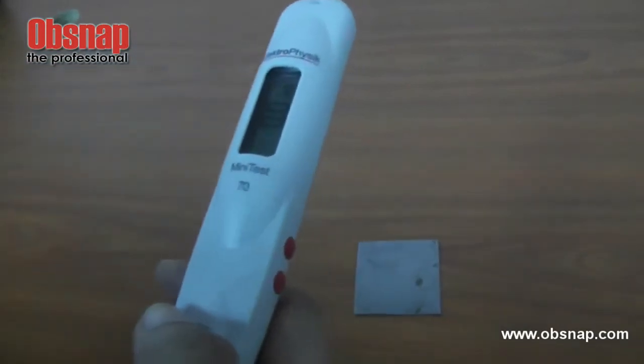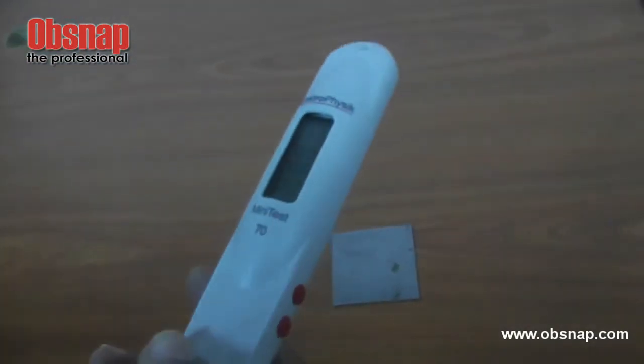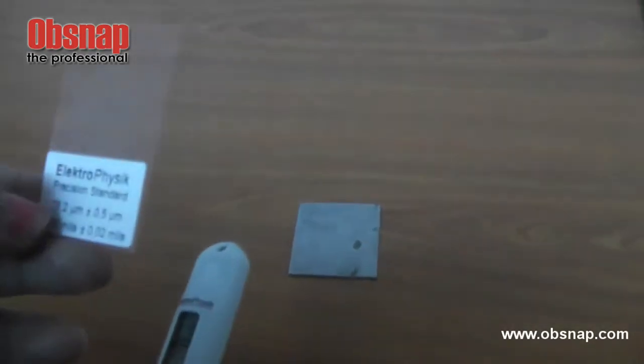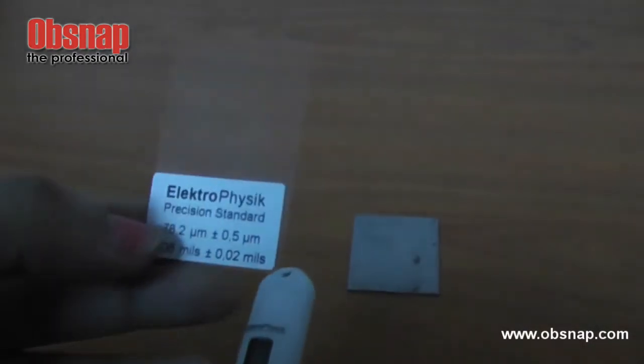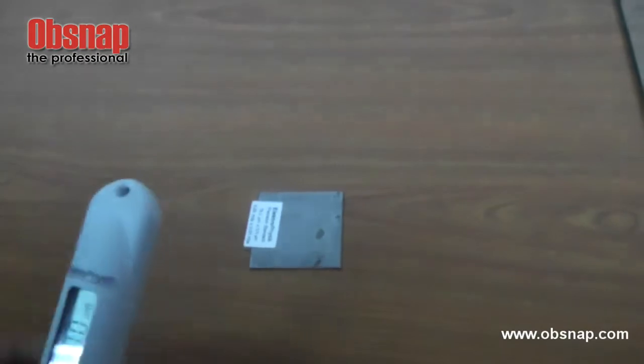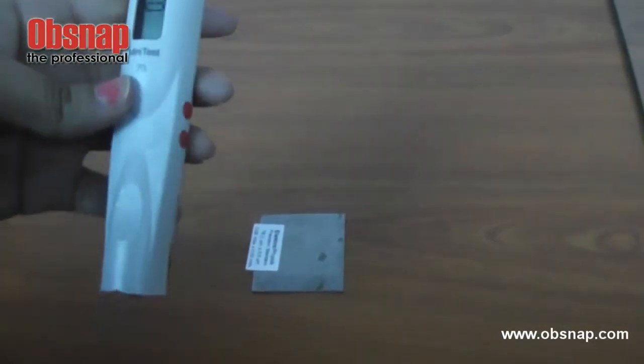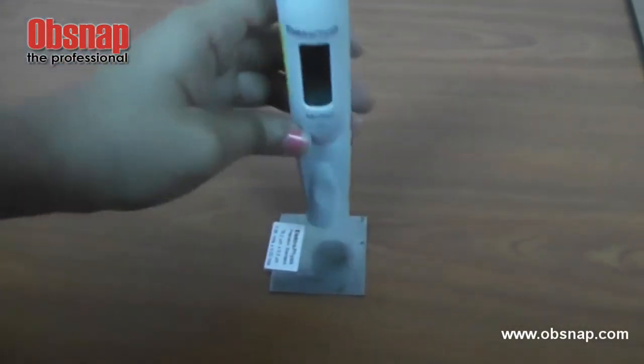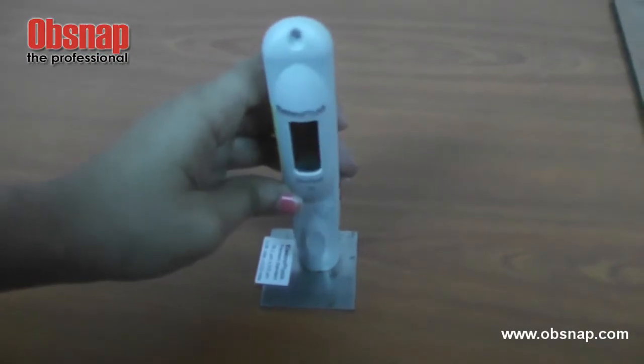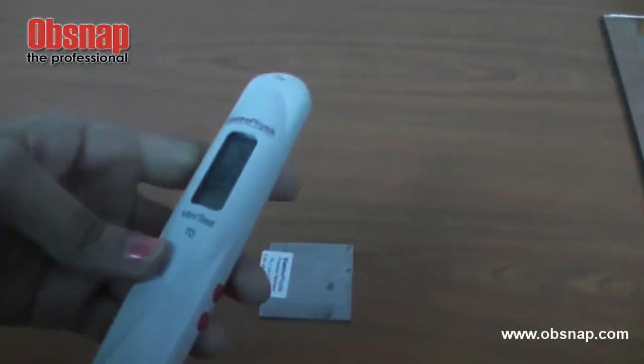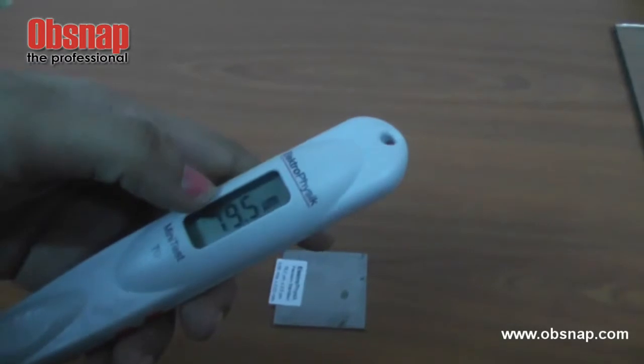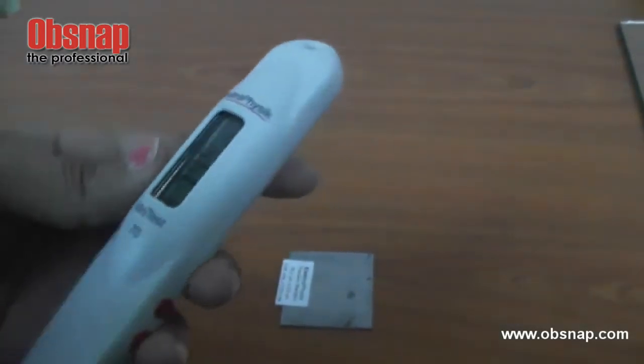Next, I'll show how to place a sample, how to test a standard sample. For example, this is the standard sample, 78.2 micrometer. I'm going to place it on this uncoated substrate, and then take the measurement, place the sensor on the sample, take the measurement, and it appears 79.5.